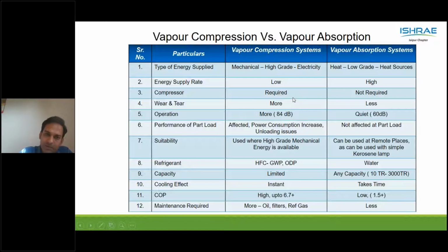Vapor compression cycles have a compressor, whereas in the absorption cycle there is no compressor as such, because the vapor absorption system has no moving parts. There is no compressor, no gear, no oil filters. Hence there is no wear and tear, which happens in vapor compression cycle systems. In terms of operation, because there are no moving parts, the sound of these vapor absorption machines is very low, about 60 decibels at 1 meter distance.